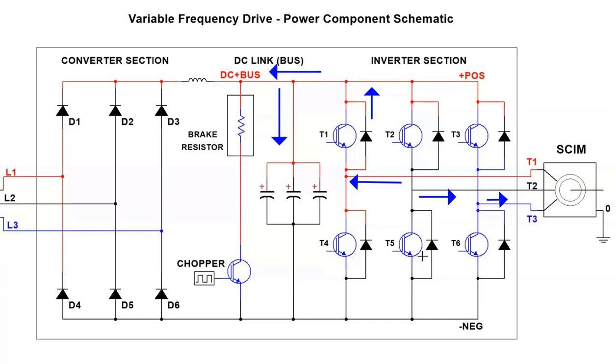You will have normally say 300 volts on the DC bus. That may go up to 400. So the difference between the positive and negative increases. It will actually pull it down and supply current back. Now it's going to switch and it's going to do this very, very quickly, the sequence of the returning energy through those regeneration diodes.